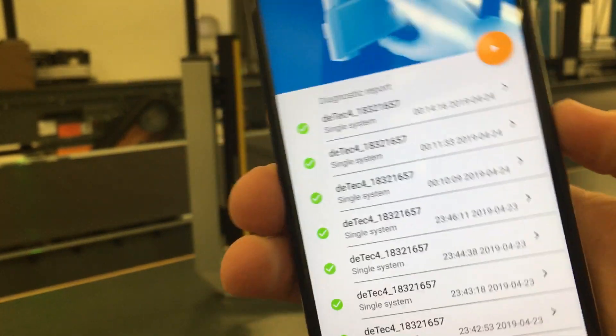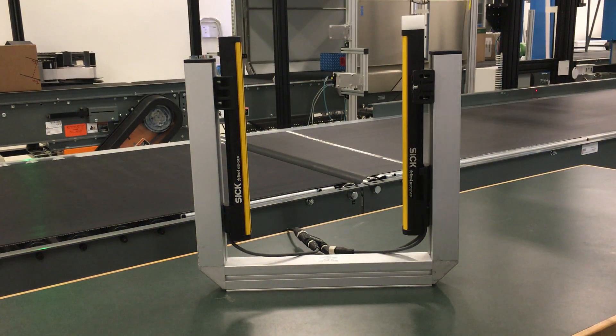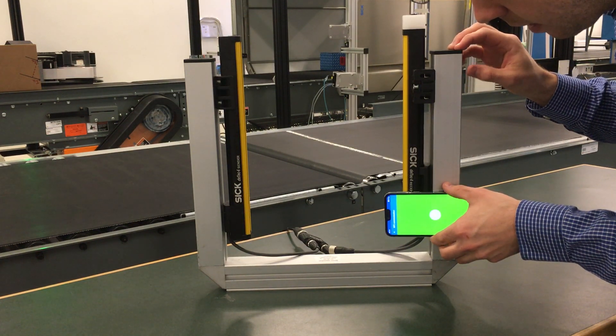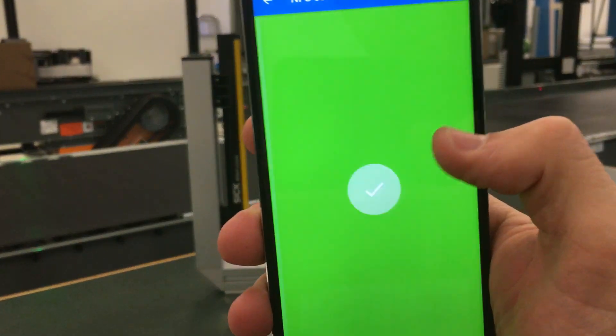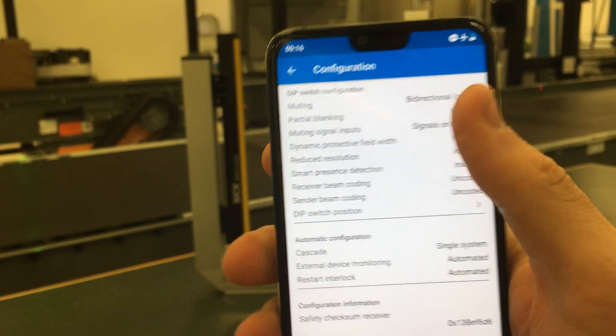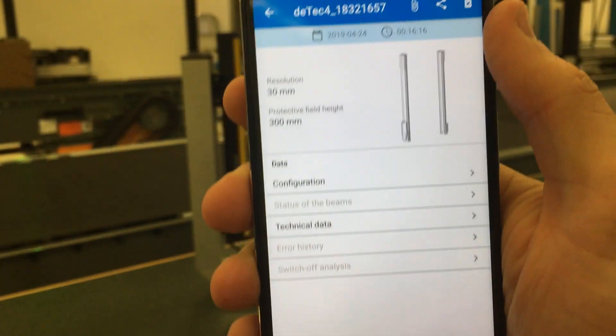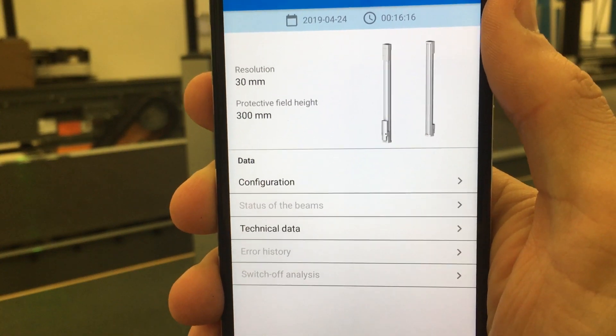One more neat feature to show you on the safety light curtain: I just powered down the safety light curtain, and even with power off, I can still see configuration information and technical data. So the new NFC feature here for the deTec4 allows you to do extensive troubleshooting in the field directly from your phone.